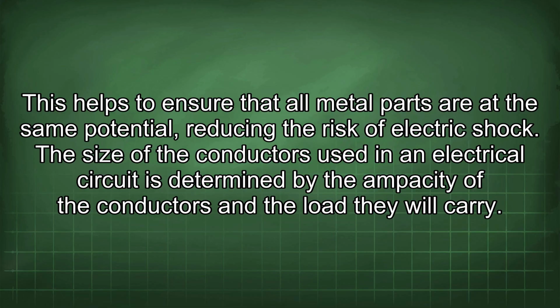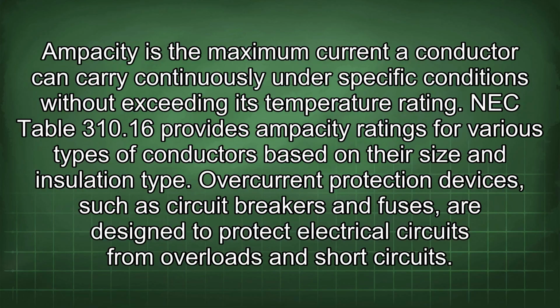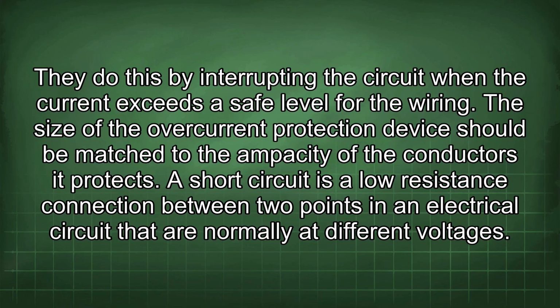The size of the conductors used in an electrical circuit is determined by the ampacity of the conductors and the load they will carry. Ampacity is the maximum current a conductor can carry continuously under specific conditions without exceeding its temperature rating. NEC Table 310.16 provides ampacity ratings for various types of conductors based on their size and insulation type. Overcurrent protection devices, such as circuit breakers and fuses, are designed to protect electrical circuits from overloads and short circuits. They do this by interrupting the circuit when the current exceeds a safe level for the wiring. The size of the overcurrent protection device should be matched to the ampacity of the conductors it protects.